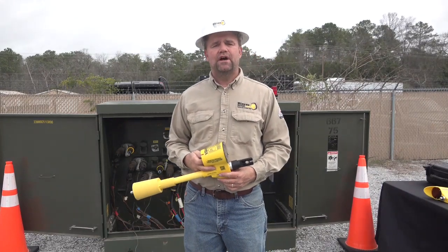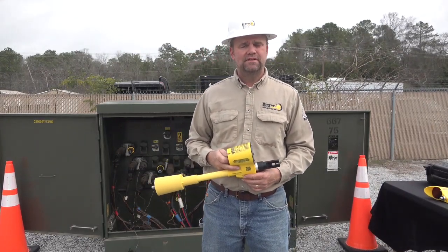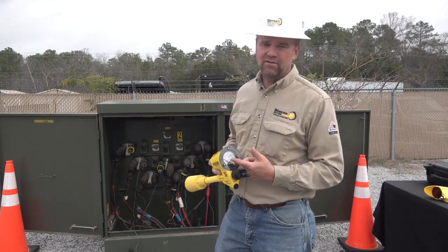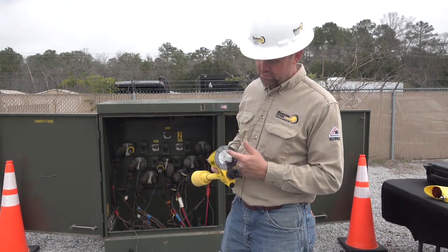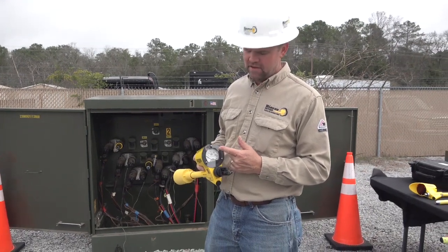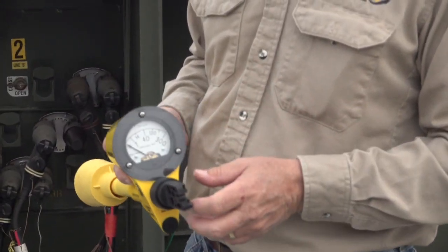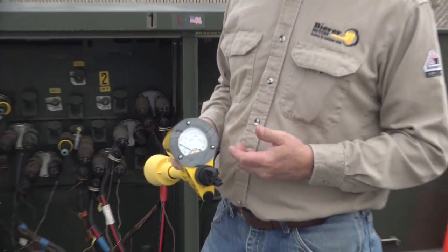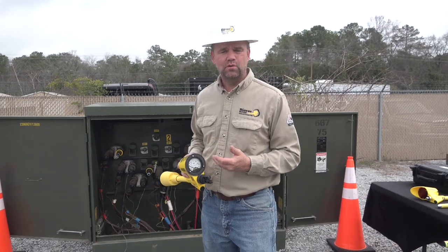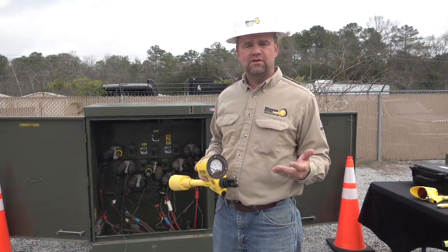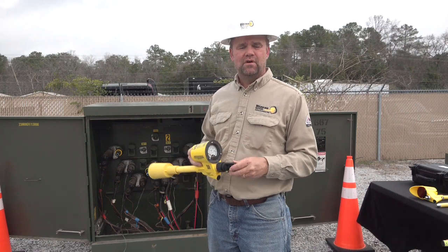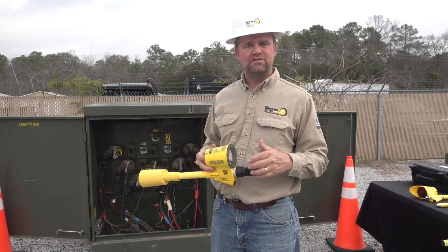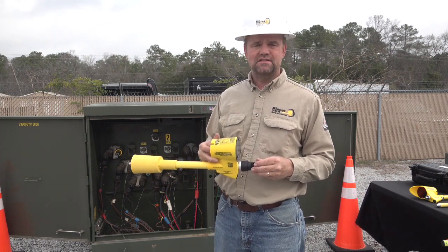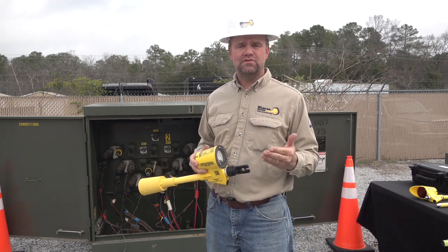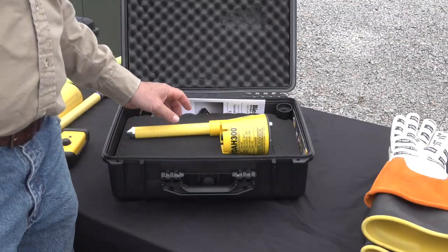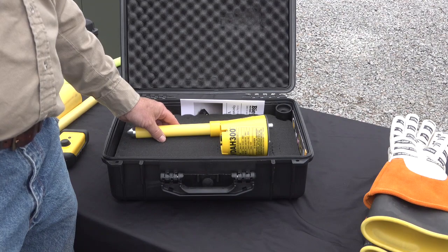The VDAH300 is a linear logarithmic meter. What that means is on the analog scale, the device is linear from 0 to 40 kV, and from 40 kV to 300 kV is logarithmic. Bierer manufactured this tool to be linear logarithmic so that the tool can be used in distribution voltages and transmission voltages while still maintaining a single-use device. Rather than having 2 or 3 devices, you can use a single device to cover distribution potentials and transmission potentials. The kit comes standard in a waterproof box.